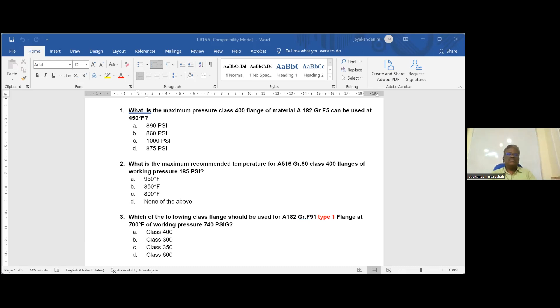Please go to hydrostatic testing, 2.6. Flange joints and flange fittings may be subjected to the system hydrostatic test at a pressure 1.5 times the 100 degrees Fahrenheit rating only. You have to check 1.5, rounded off to the next higher 25 psi increment. Testing at any higher pressure is the responsibility of the user, taking into account. So generally, if you want more pressure, the user will decide. This is marked as open book, so try to attend this question.